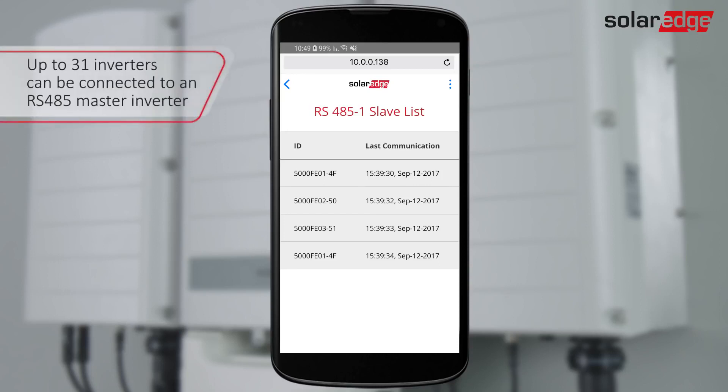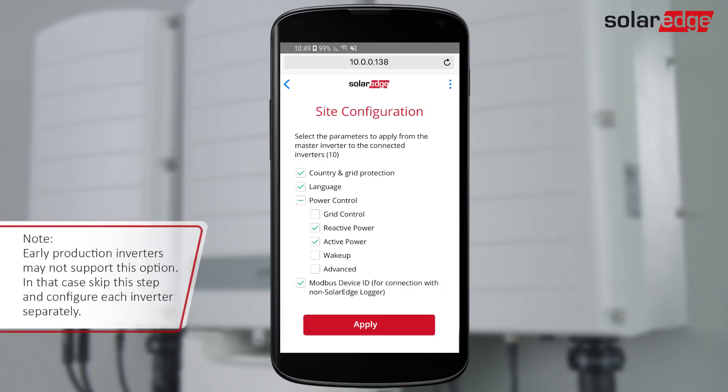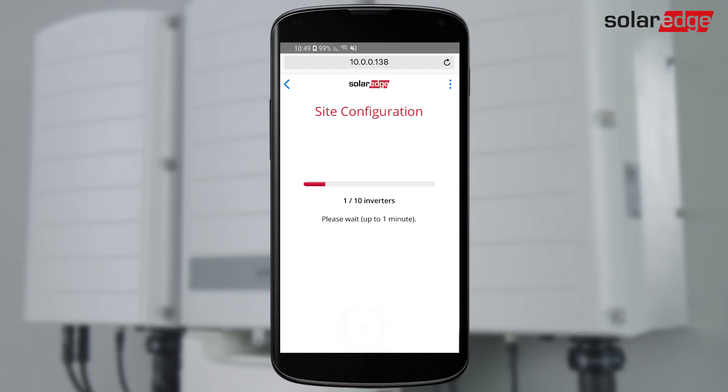Can be configured simultaneously from the master inverter. Enter the site configuration menu for applying master inverter settings to other inverters on the same RS-485 bus. Tap Apply. All inverters on the bus are configured simultaneously. When the site configuration is complete, tap OK.